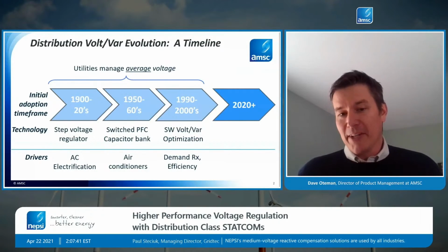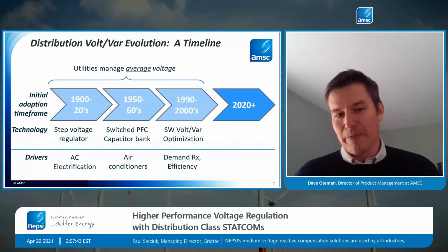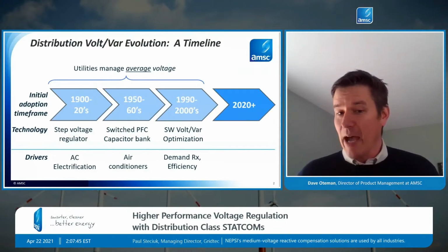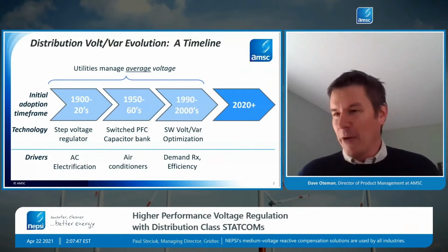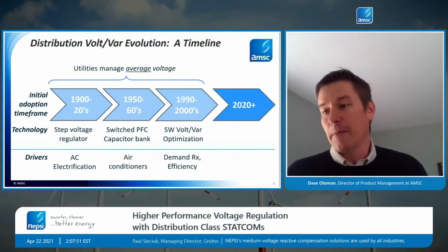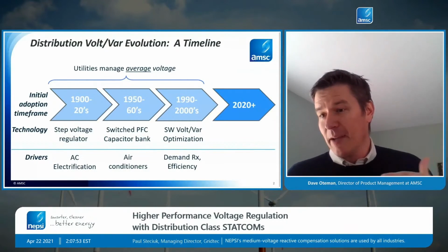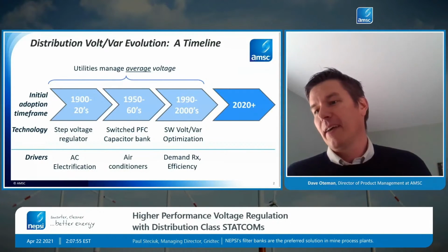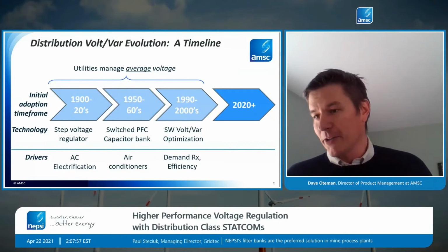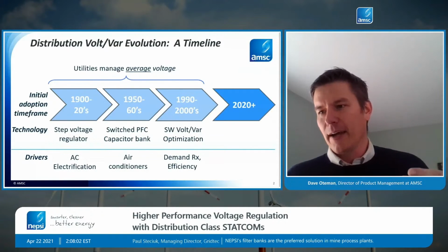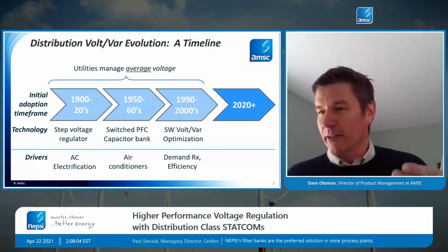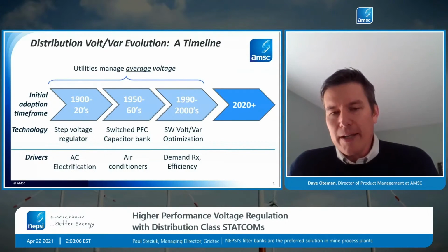So the utility system now has a combination of step voltage regulators as well as switched cap banks installed, thousands of devices on most larger utility systems. Then this really became the era of efficiency, and not just in volt-VAR control, but across the board, more efficient appliances, more efficient lighting. Obviously, LEDs started to come of age towards the second half of this.